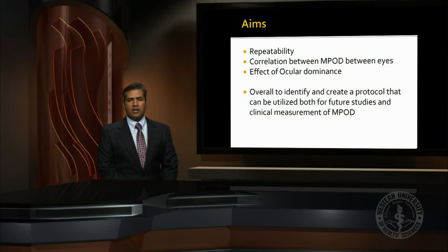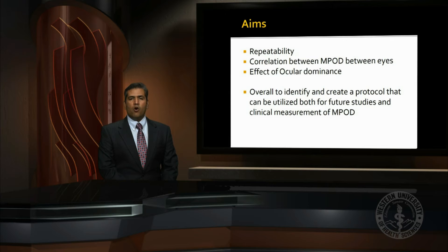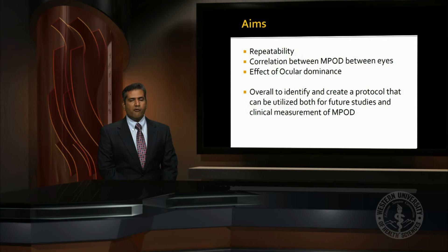We evaluated a heterochromatic flicker photometer for its repeatability, correlation of results between eyes, and the effect of ocular dominance. The overarching goal was to evaluate and create a protocol that could be utilized both clinically as well as for future research studies.